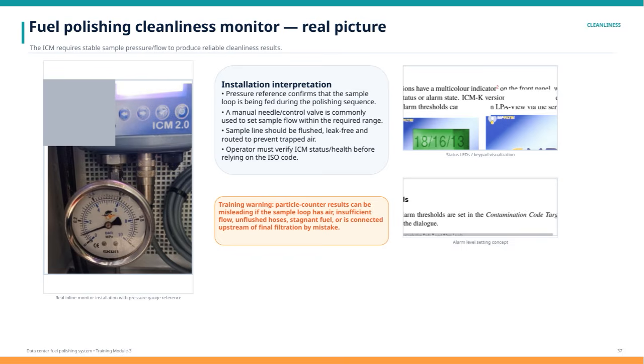Additionally, the operator must always check the ICM status and health before trusting the ISO cleanliness code displayed. The monitor's status LEDs and keypad visualization provide real-time feedback, making it easier to interpret data and respond quickly if issues arise. There is also an alarm level setting concept in place to alert operators when cleanliness parameters fall outside acceptable limits. Finally, a key training reminder. Particle counter results can be misleading if the sample loop isn't set up correctly. Problems like trapped air, insufficient flow, unflushed hoses, stagnant fuel, or incorrect connection points can all affect the accuracy of the readings. Proper training and careful maintenance are therefore essential for reliable fuel polishing results.